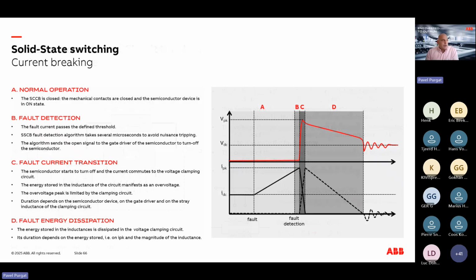So when we look at the operation waveforms of a solid-state circuit breaker, we see that the current is flowing through the main semiconductor device. We detect a fault, and here it's important also to say that the fault detection period is mostly defined by the time we need to make sure that there is a short circuit. As I said, in DC systems you will have a lot of interruptions, various currents. Because the threshold of the short circuit in DC is quite low, it can happen that some spurious or switching event momentarily increases the current above your threshold, but you should not trip immediately. So the time that you need to interrupt the short circuit current is very often dominated by the time you need to make sure that indeed you are in a short circuit scenario.